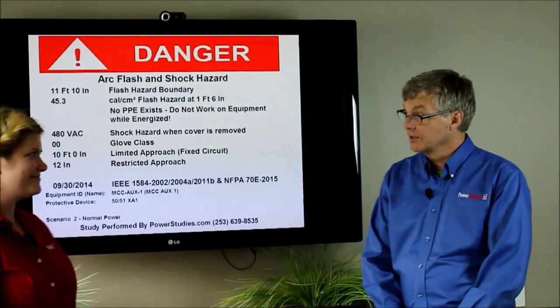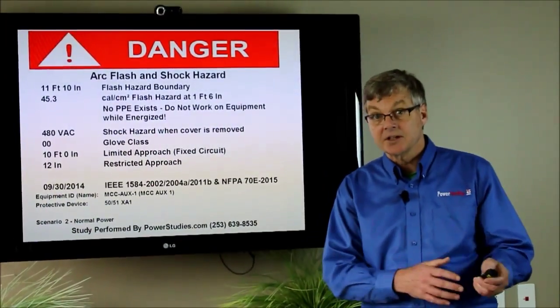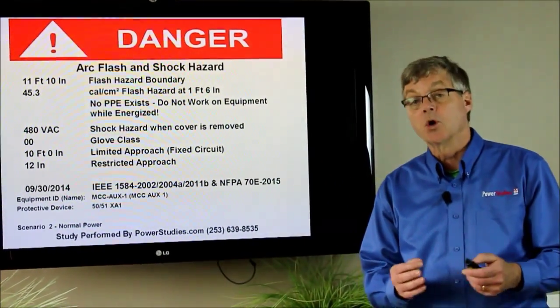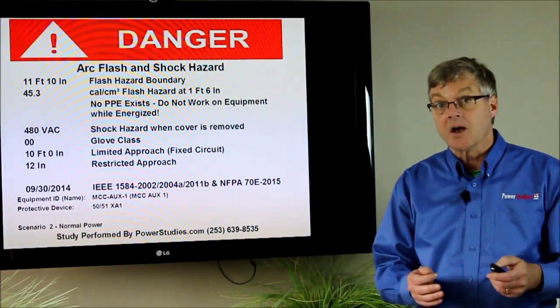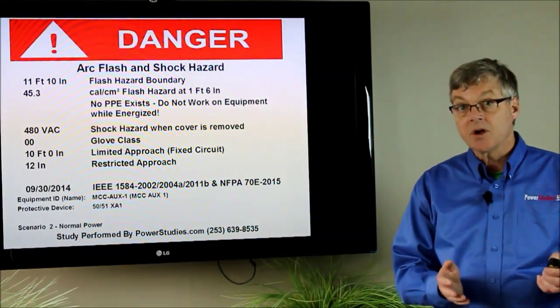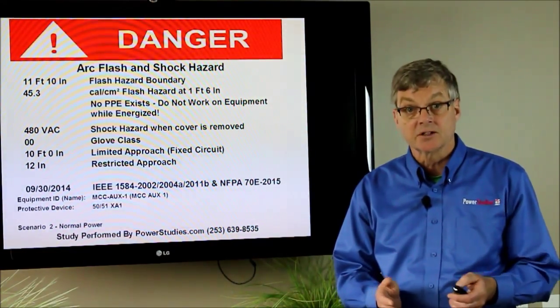Well that's a great question and actually the answer is they are the same. An incident energy analysis and an arc flash study is the same thing. The goal is to calculate the arc flash energy and the arc flash boundary, and then once you know what the arc flash energy is, you can select the appropriate PPE to protect you from the hazard.